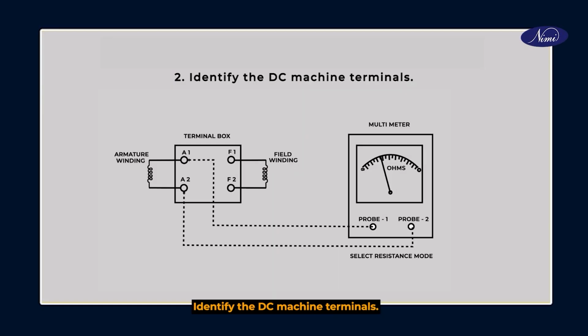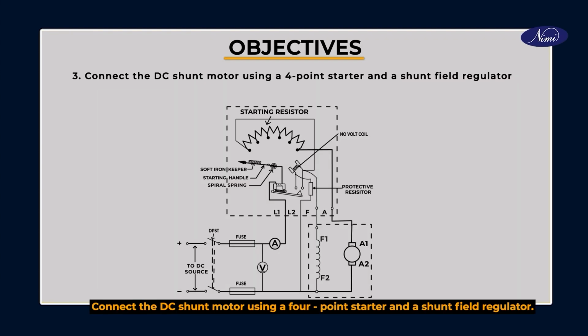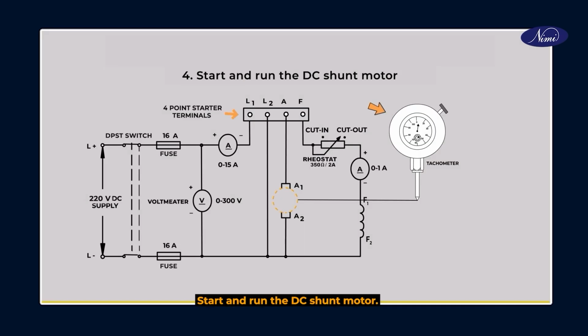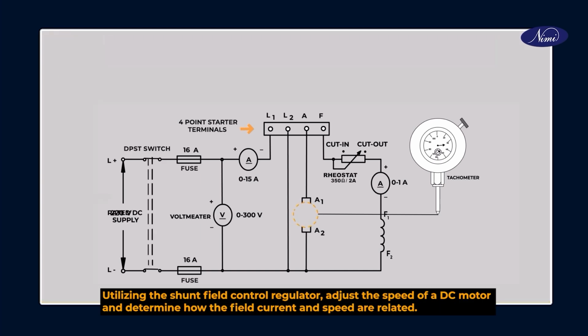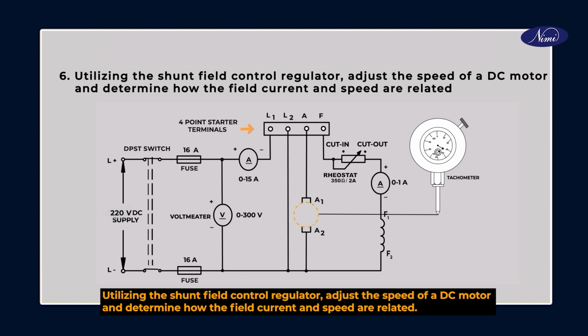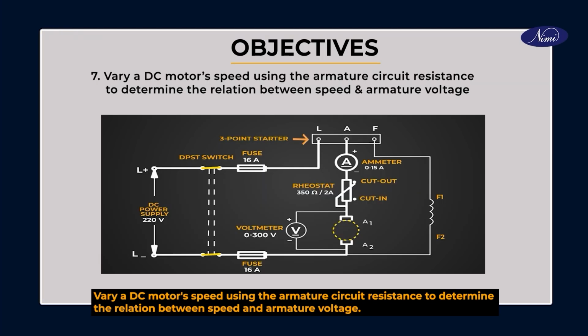Recap: in this session, we understood how to comprehend and apply the information on a DC machine's nameplate, identify the DC machine terminals, connect the DC shunt motor using a 4-point starter and a shunt field regulator, start and run the DC shunt motor, and measure the speed of the motor. Utilizing the shunt field control regulator, adjust the speed of a DC motor and determine how the field current and speed are related. Vary a DC motor's speed using the armature circuit resistance to determine the relation between speed and armature voltage.